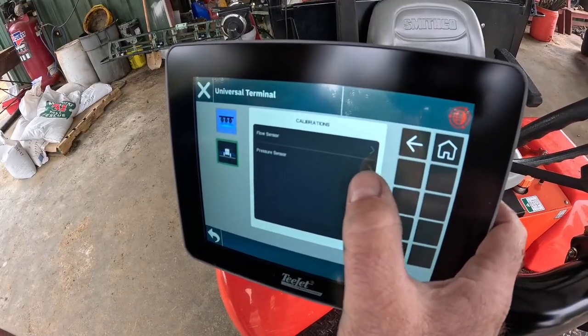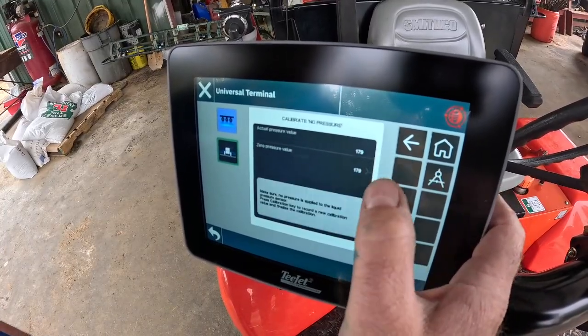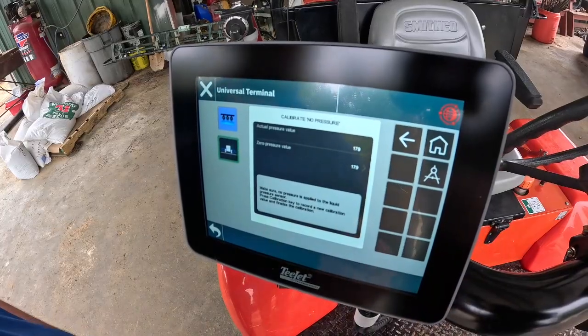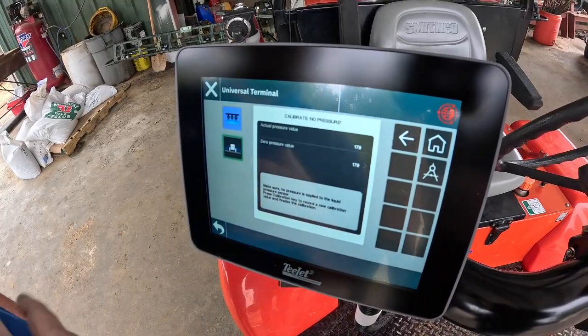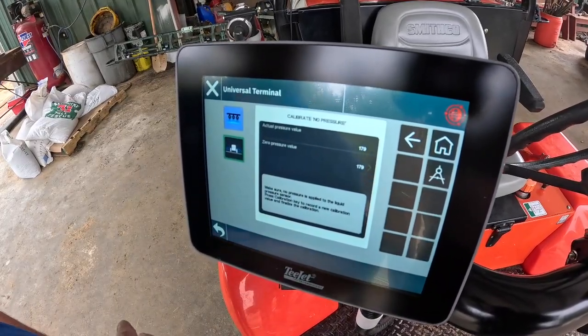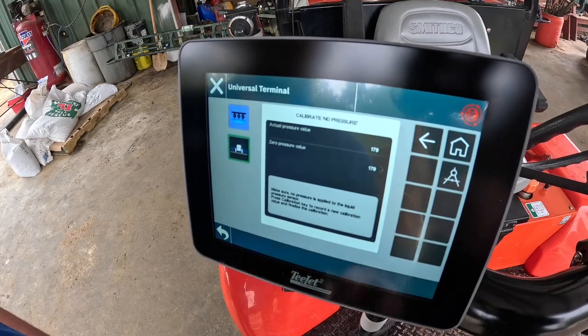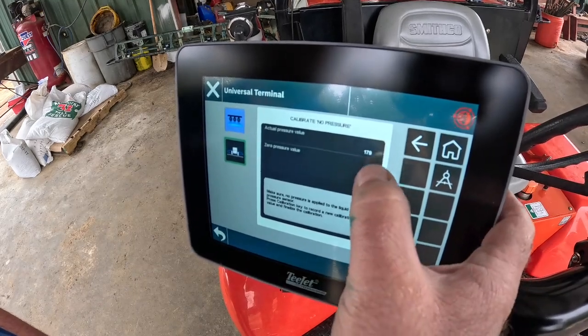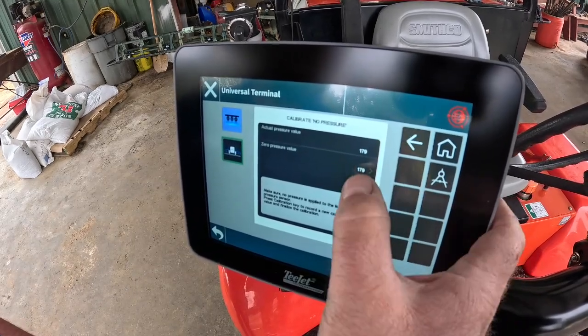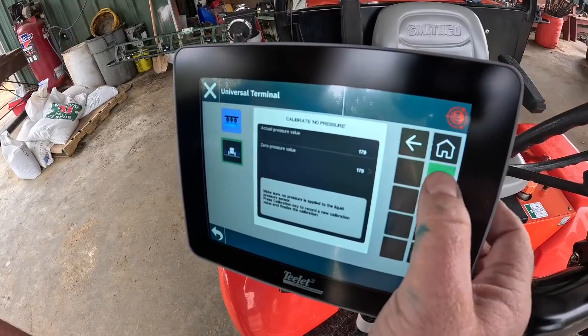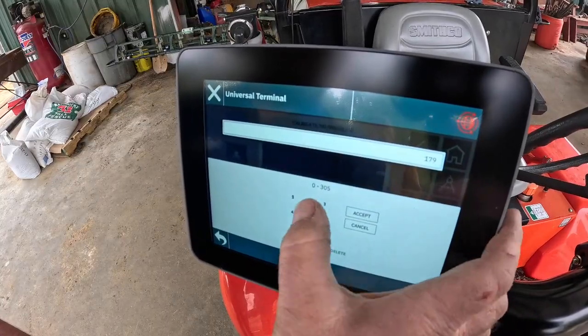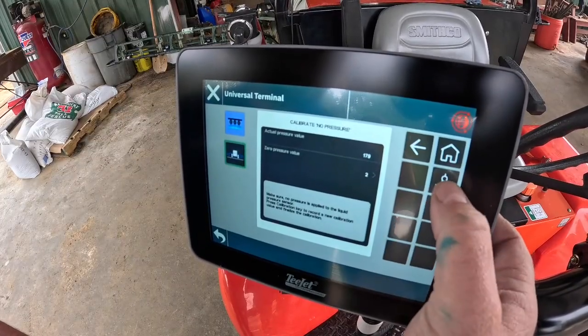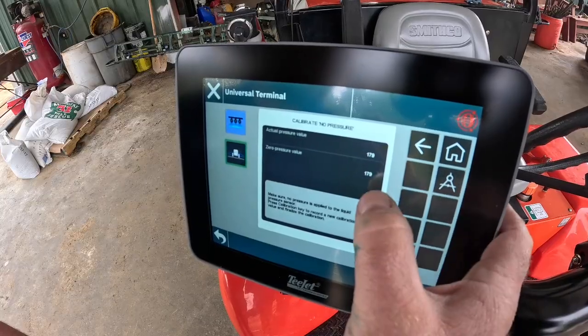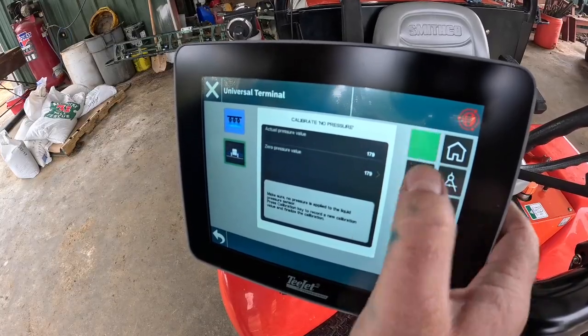We also have our pressure transducer, and you have to calibrate your no pressure, and you do that with the machine. The engine can be running, but have the pump turned off. Make sure you're not spraying. Your system has no pressure on it. As you can see, both of ours are the same right now, but you hit this calibration button and it would change it. So for instance, I can change that to that, and then I can hit the calibration button and it would auto calibrate it for you.